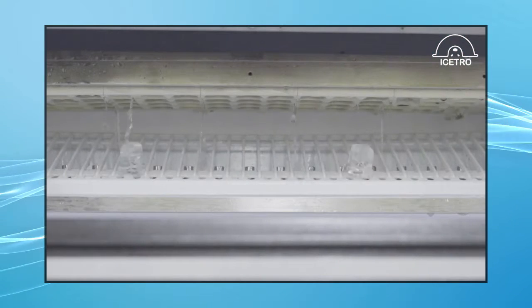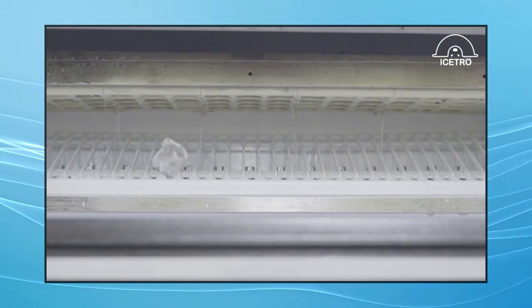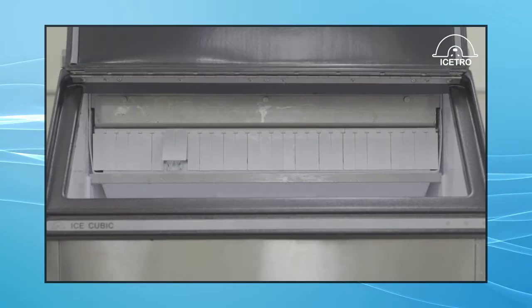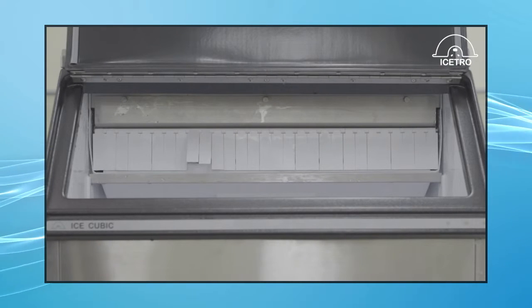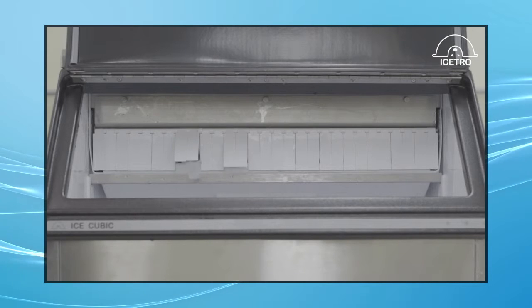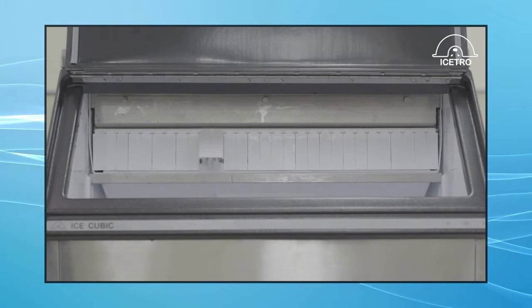And once the evaporator thermostat reaches 55 to 64 degrees Fahrenheit, the defrost mode is terminated. The freeze cycle starts over again and this sequence repeats itself until the bin sensor senses a full bin and the ice maker will shut down.